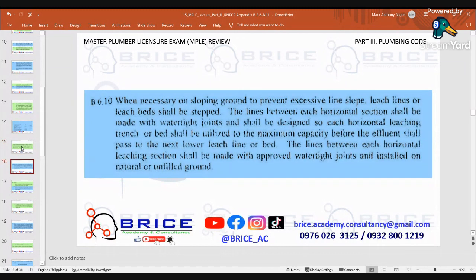When necessary, on sloping ground to prevent excessive line slope, leach lines or leach beds shall be stepped. The lines between each horizontal section shall be made with watertight joints and shall be designed so each horizontal leaching trench or bed shall be utilized to the maximum capacity before the effluent shall pass to the next lower leach line or bed. The lines between each horizontal leaching section shall be made with approved watertight joints and installed on natural or unfilled ground.